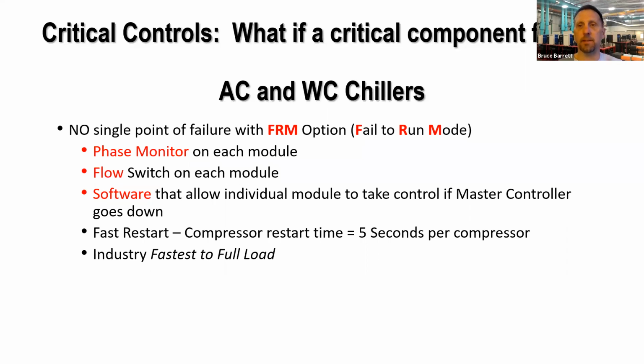We're not relying on that singular item for failure to bring your entire chiller plant down. We also add software. If your master controller burns up, our slave controller will take over making chilled water out of that module. So if you've planned for maybe an additional module or two, add the fail to run mode component, or we call FRM, phase switch, phase monitor, flow switch, and software. You can have your chiller plant run even though you've got a single component down.